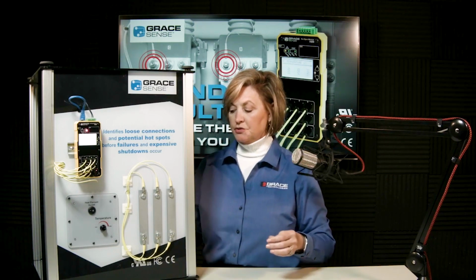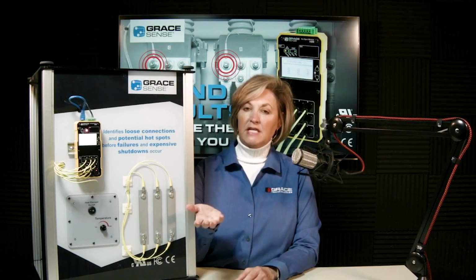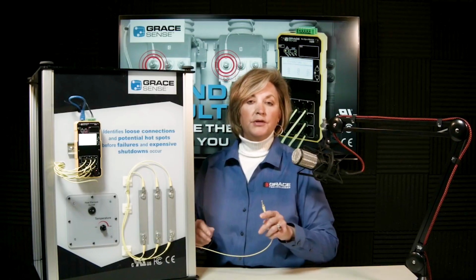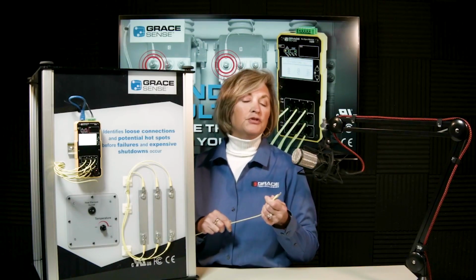The HSM probes come in 2 lengths, either 10 meters or 15 meters. What we typically choose to provide in the standard kit is a 10-meter length of fiber, and that typically gets anywhere within your electrical equipment that's needed. We kit it in that length because OEMs, for example, that are manufacturing switchgear or motor control centers, find 10 meters is plenty to get anywhere you need to go. Typically in field applications, since sometimes it's unknown, the 15 meter is the better one to get. They're all calibrated to the full length, so it doesn't matter if you trim it or not.